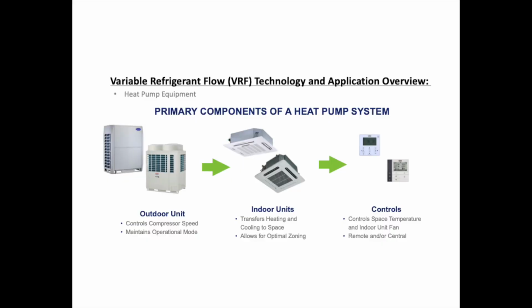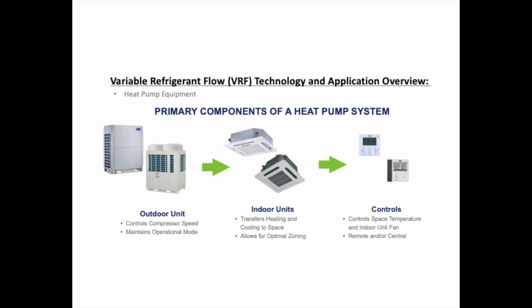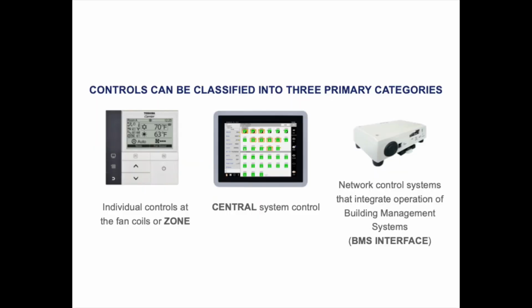Let's look at the primary components of a heat pump system. You have your outdoor unit, your indoor units, and your control system. The outdoor unit is what controls the compressor logic. It maintains the operational mode, so it'll tell the indoor fan coils whether you're in a heating or in a cooling mode. Your indoor units transfer hot air or cold air into the space, and this is what allows for optimal zoning. You can apply a fan coil unit to each individual zone for greater levels of comfort and control. And your controls monitor the space temperature and control the indoor fan coil. We have different types of remote controllers, and we also have remote and central controllers.